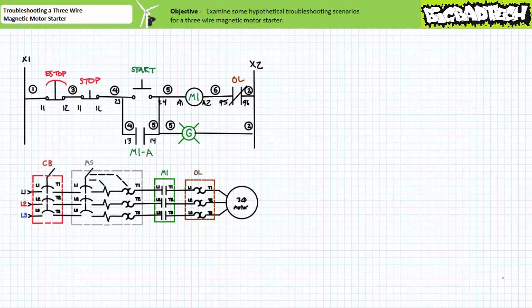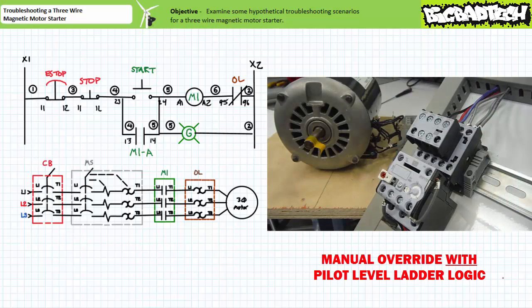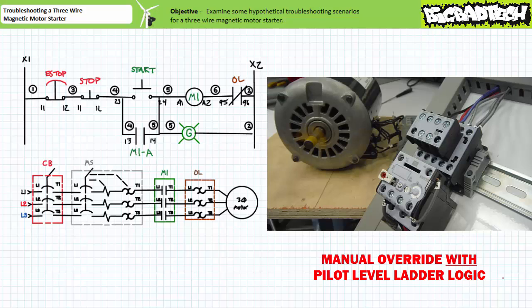The behavior of the manual override is fundamentally and dangerously different when the pilot level ladder logic is functional. As previously, the manual closure of the contactor results in the motor starting. However, when an operator releases the manual override, the contactor remains pulled in and the motor continues to run because the holding circuit has been established.